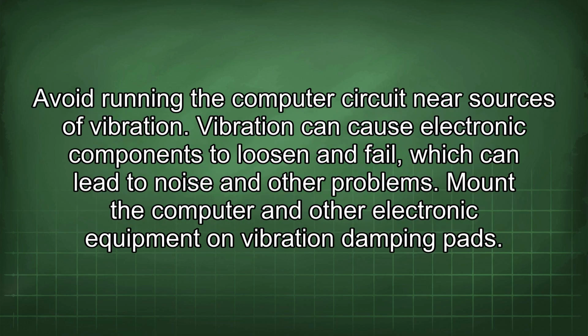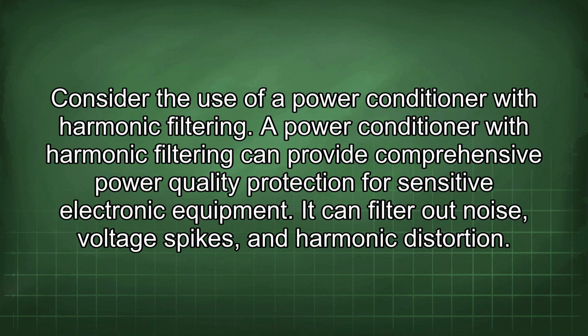Avoid running the computer circuit near sources of vibration. Vibration can cause electronic components to loosen and fail, which can lead to noise and other problems. Mount the computer and other electronic equipment on vibration damping pads. Consider the use of a power conditioner with harmonic filtering. A power conditioner with harmonic filtering can provide comprehensive power quality protection for sensitive electronic equipment. It can filter out noise, voltage spikes, and harmonic distortion.